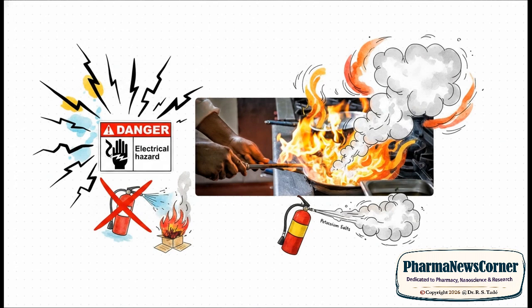To give you an idea of why those classifications are so crucial, let's contrast a couple of distinct hazards. On one side, we have an electrical hazard, and on the other, a super volatile Class F cooking oil fire in a commercial kitchen. If you've just got a simple Class A paper fire, a standard water extinguisher is perfect. But spray water on a live electrical box? Yeah, you just became a conductor. Or spray water into 340-degree auto-ignited cooking oil. The water instantly turns to steam, expands rapidly, and creates this massive fireball. You need entirely different chemistry, like wet chemical extinguishers utilizing potassium salts to safely smother that oil.